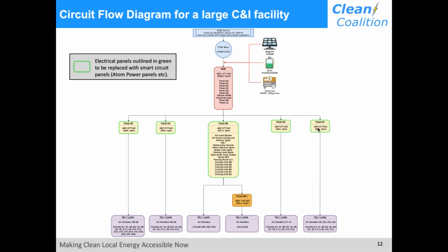So these smart panels that I'm indicating, the 5 of them, they have tier 1, tier 2, and tier 3 loads on them. Each one of those, we need to be able to program, and maybe even dynamically change those settings on the fly. When a grid outage happens for a long duration, you may change what your priorities are, and the smart panels can do that, turning individual circuits on and off through this scheme.